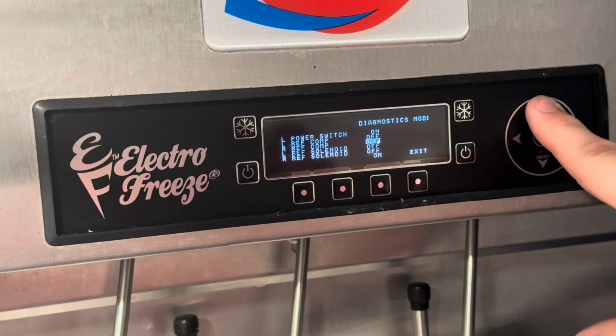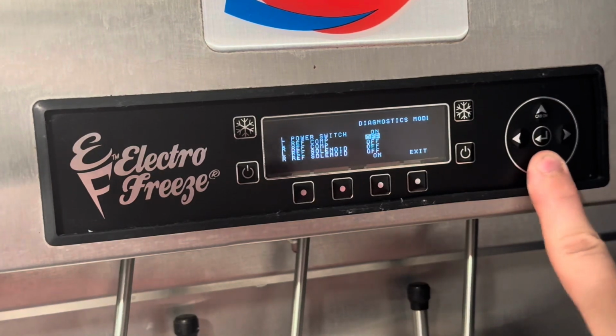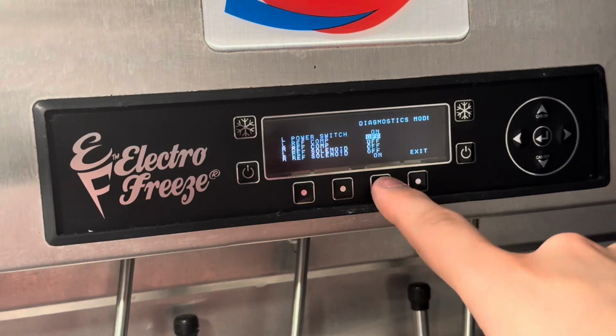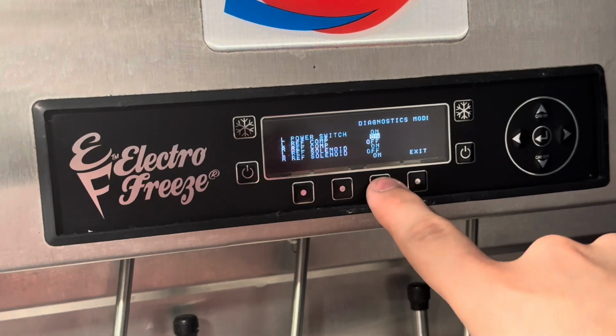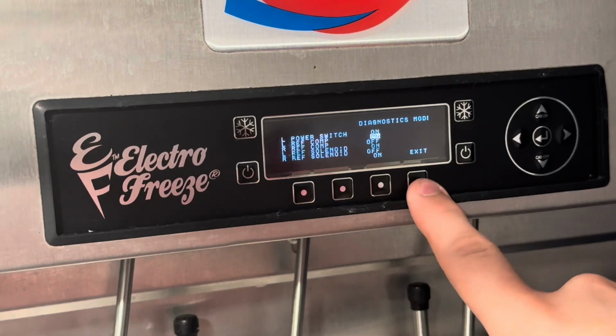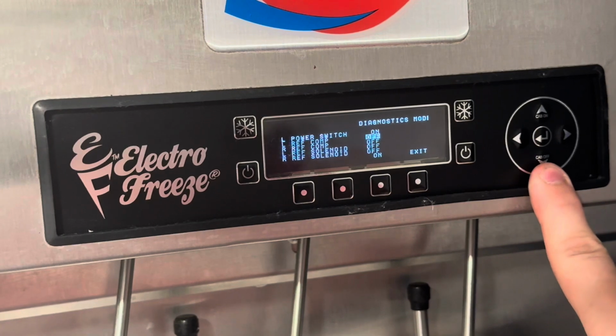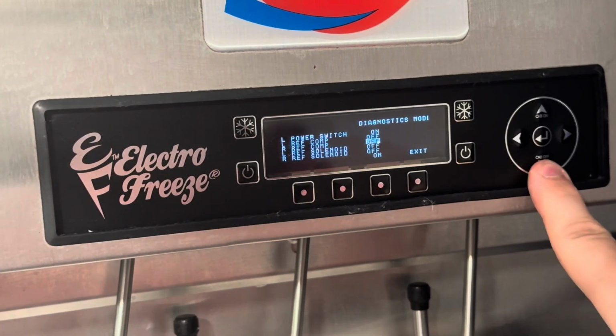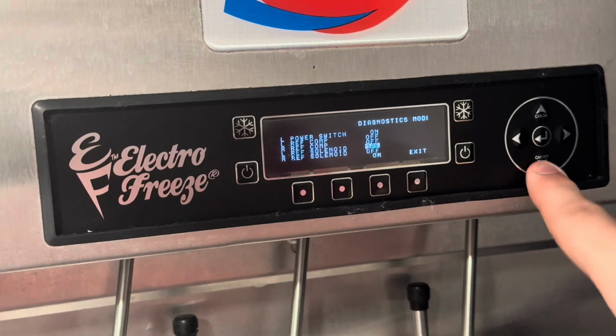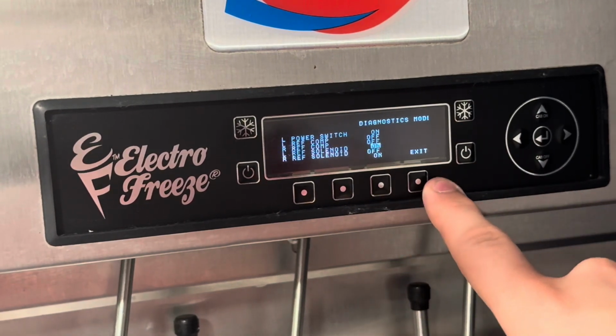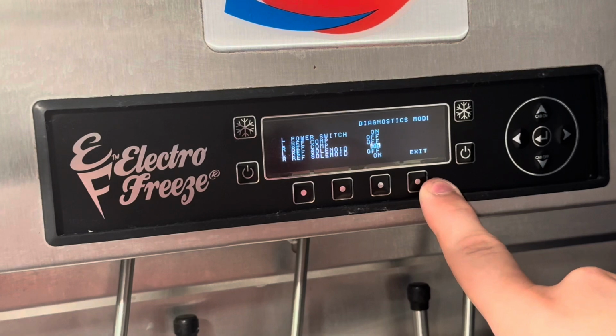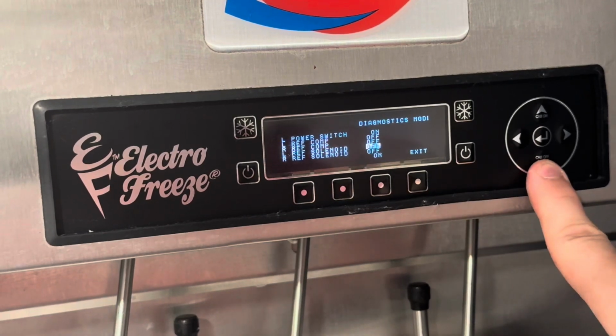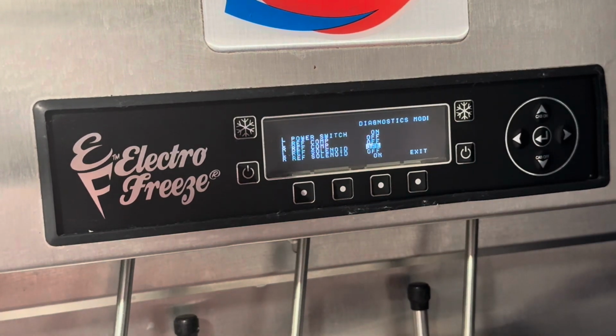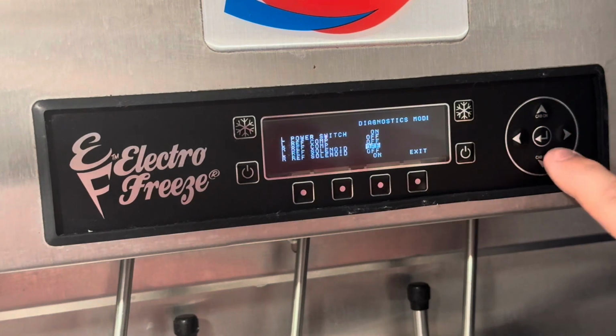So we've got the compressors, we could press on to turn it on, and then it shuts off. Same with all these, the refrigeration solenoid, we can press on, that's going to open it, and then it'll stop in a second. That's very useful to test each component of the machine if you feel there's a problem with that component.